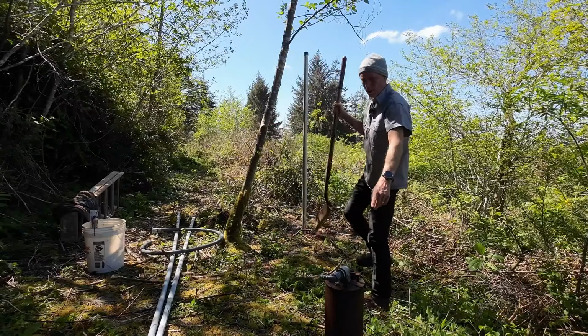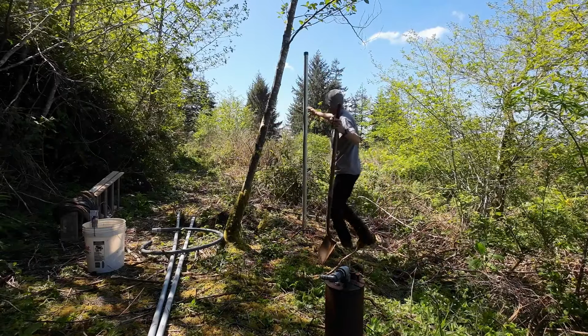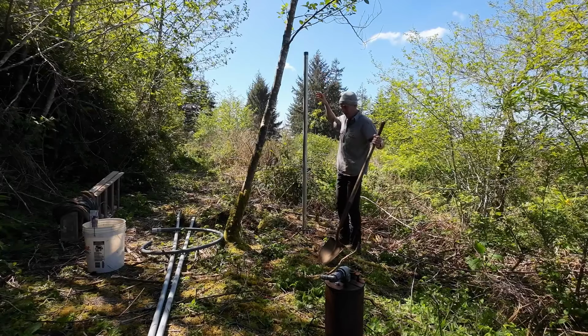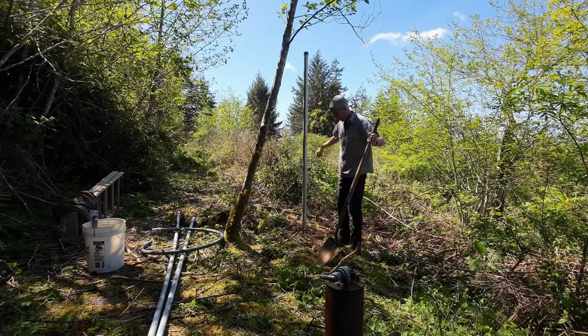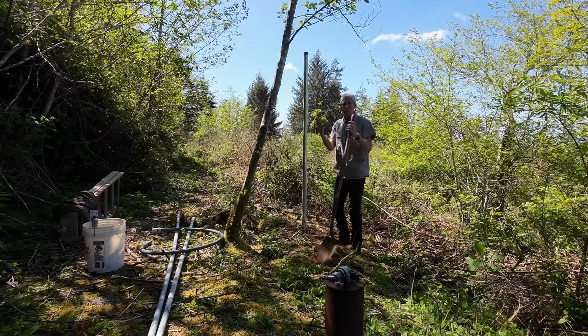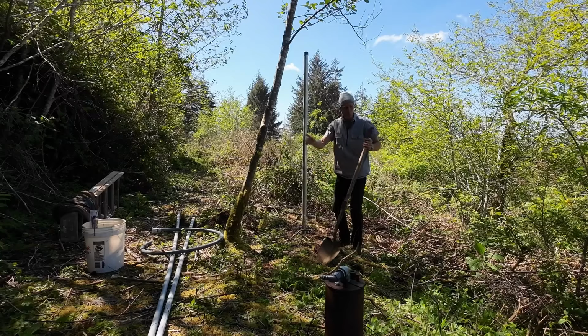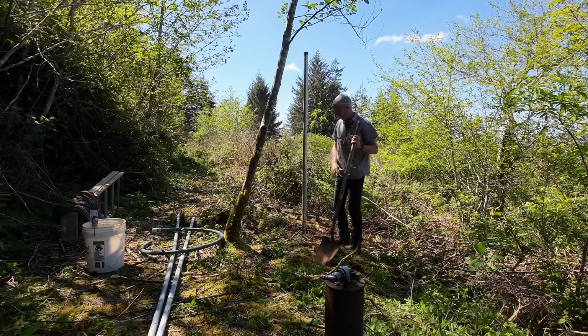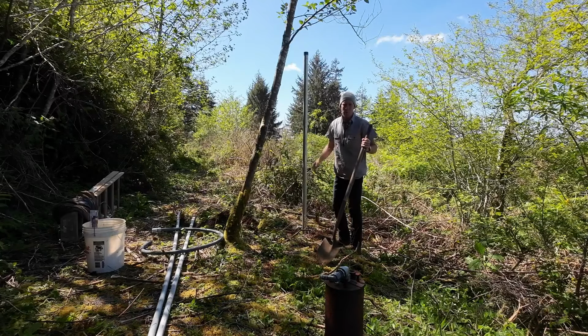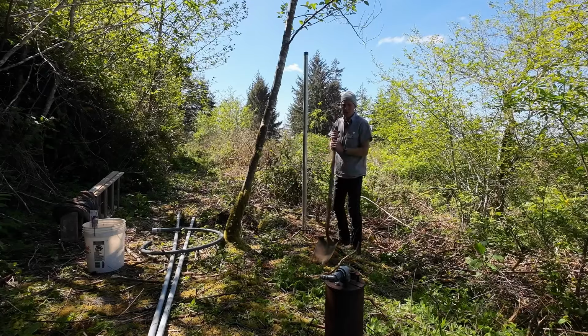All right, so we got a pump here, and it's gonna have a controller that's gonna be mounted on the pole over here with the solar panels up above. And so I'm gonna just dig a little trench across, put in this PVC and a little flexible whip at the end so that we can pull the pump pretty easily with that flexible part, but then have this buried so that animals walking through here or anything going on doesn't disturb the wiring. The wiring's submersible and it's underground rated, but it'd just be nice to be able to pull it through that conduit.